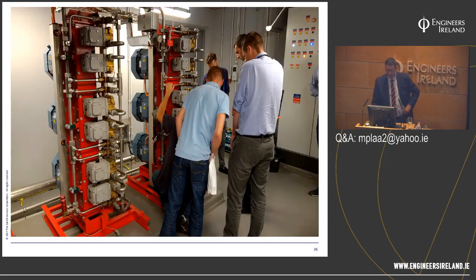And one of the other things that's really important to do on this is a system where I asked the installer to undertake testing of the pumps. So we'll go actually check the pressure and flow of each of the pumps. In this particular case, the pumps delivered the correct pressures and flows that was needed, but it was important as part of the verification that the installer could show me on the flow meter. We'll run the pumps through various stages and make sure we got exactly what the system was intended to provide. So try and get on site and verify that the pump set delivers the correct pressures and flows, and be there, be challenging, be tenacious and check them.